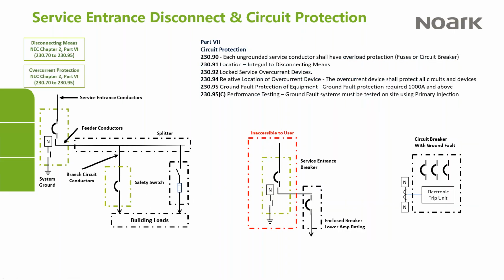Getting close to the end here, so I know we're at the end of our time. This is the last part of it where I'm going to talk about the circuit protection requirements. So each ungrounded service conductor must have overload protection. So that means a circuit breaker or fuses. The circuit protection has to be integral to the disconnecting means. So that means it has to be inside the box. And with a circuit breaker, of course, that's all inside the circuit breaker.